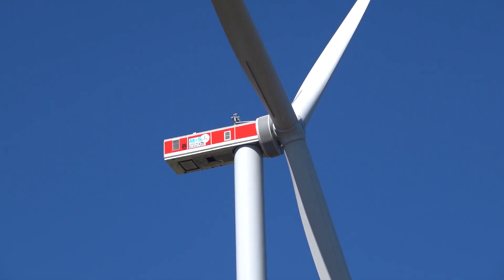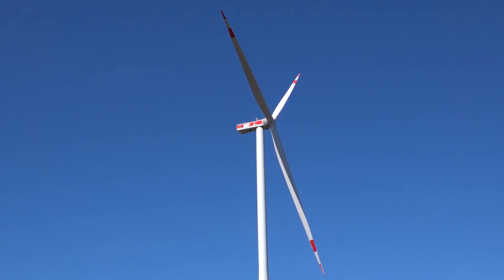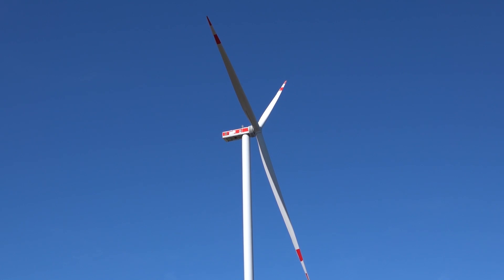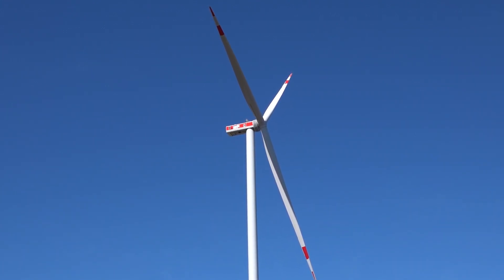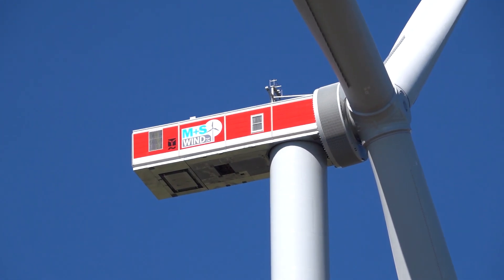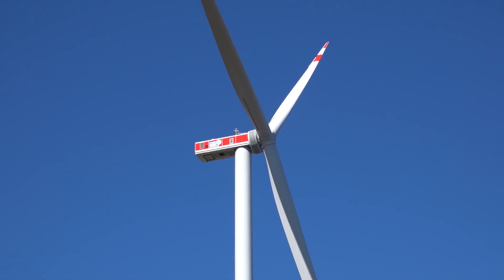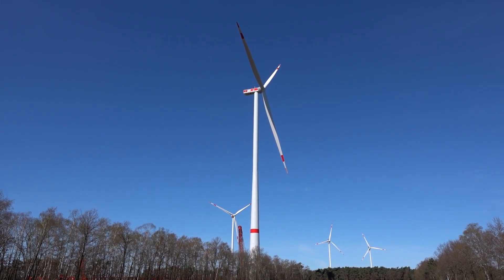M+S Wind is one of the shareholders of the wind farm. The E-Nacelle comes with a lot of advantages — production costs are cheaper, transport and logistics are easier, and installation is also faster because the E-Nacelles are already fully cabled and tested at the factory. There is no installation of a separate E-module in the tower base needed anymore. That means transmission losses from the tower to the E-module are greatly reduced, and therefore the nominal power also increases from 5.5 to 5.56 megawatts. They also switched the cables from low to medium voltage, which speeds up the commissioning process.